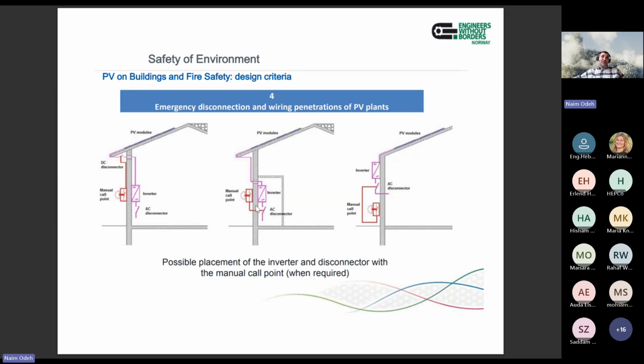The other scenario of the manual call point is to have AC disconnection. If you notice here, we are considering this as if the inverter is inside the building, so the manual call point is always outside, but it's important to be protected so you don't have it open to everyone who comes there, but in case of emergency, anyone can come and disconnect it. So these are different scenarios. The last two depend on the AC disconnection, just to protect the content of the house only. The first one depends on securing the content of the house, including the inverter if it is inside the building.